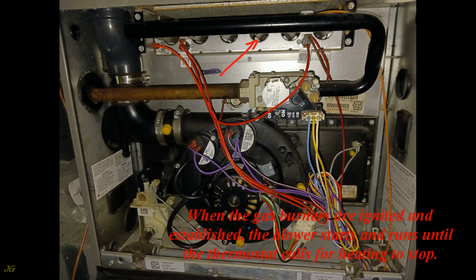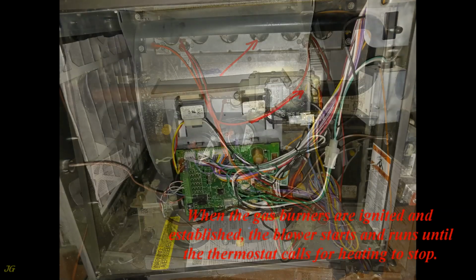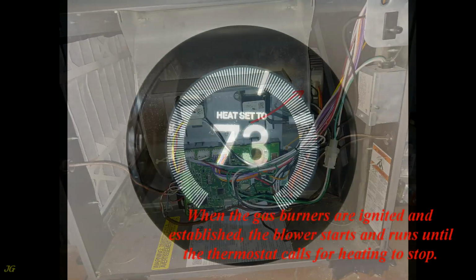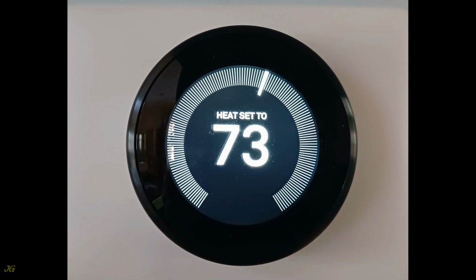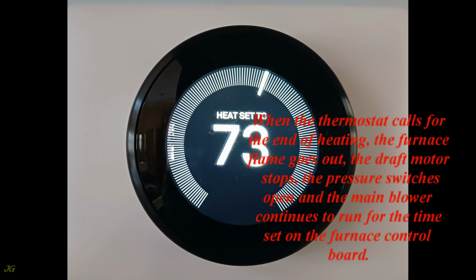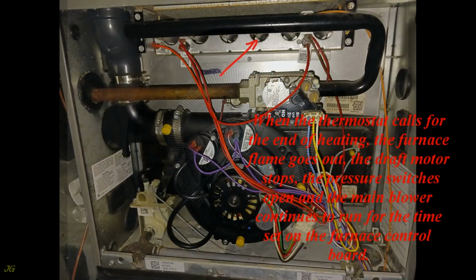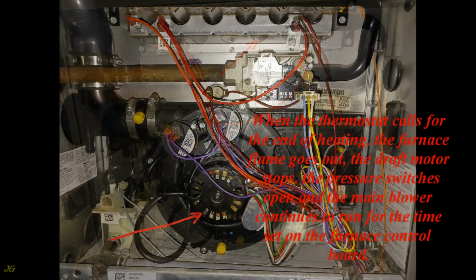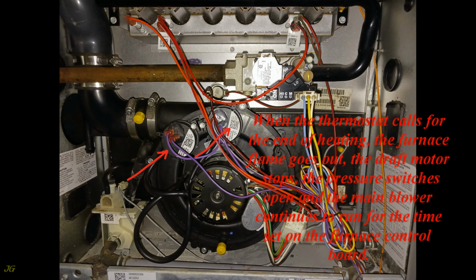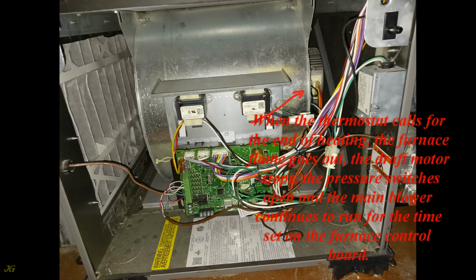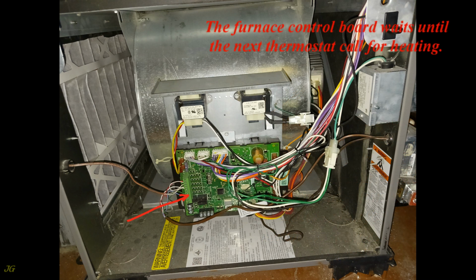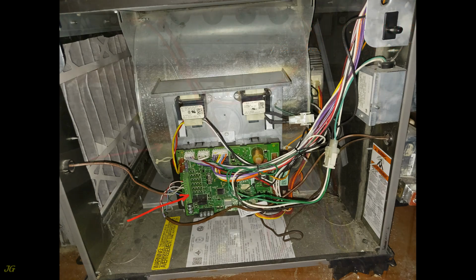When the gas burners are ignited and established, the blower starts and runs until the thermostat calls for heating to stop. When the thermostat calls for the end of heating, the furnace flame goes out, the draft motor stops, the pressure switch is open and the main blower continues to run for the time set on the furnace control board. The furnace control board waits until the next thermostat call for heating.